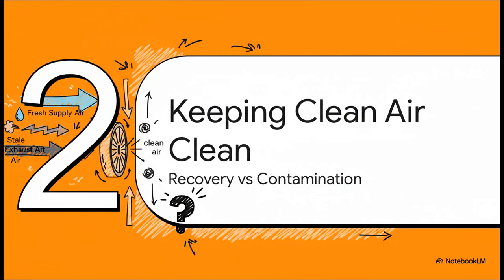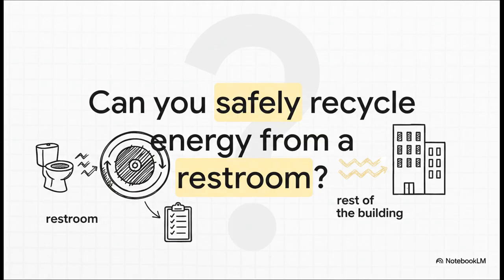Okay, so we've established the wheel is incredibly efficient, but this brings us to its first major challenge. You're taking stale, potentially germ-filled exhaust air and passing it inches, literally inches away from your fresh supply air. So how in the world do you recover the energy without mixing all the bad stuff back in? Let's make this real. Can you safely take the air you're pulling out of a public restroom, run it through one of these wheels, and not contaminate the fresh air you're about to pump into the rest of the building?